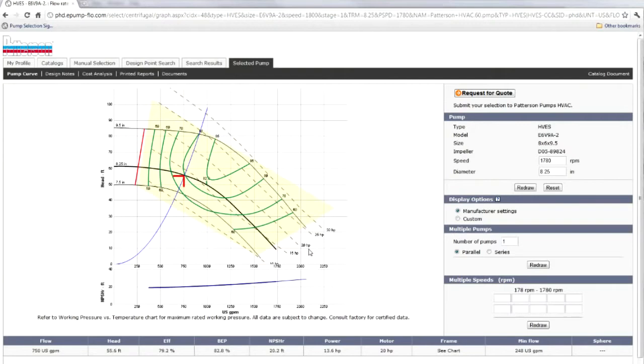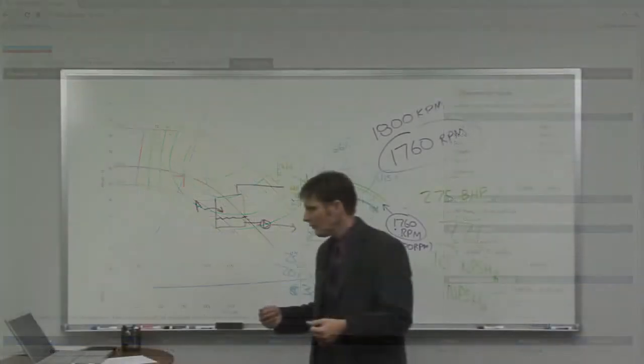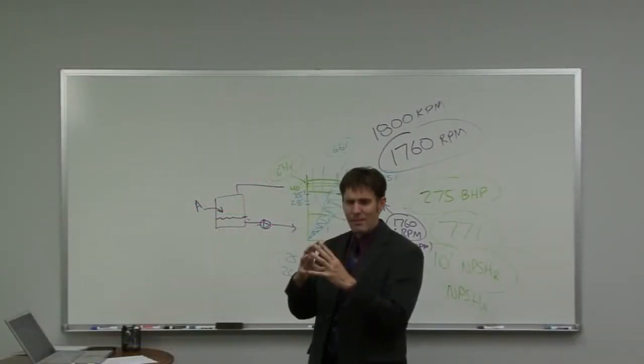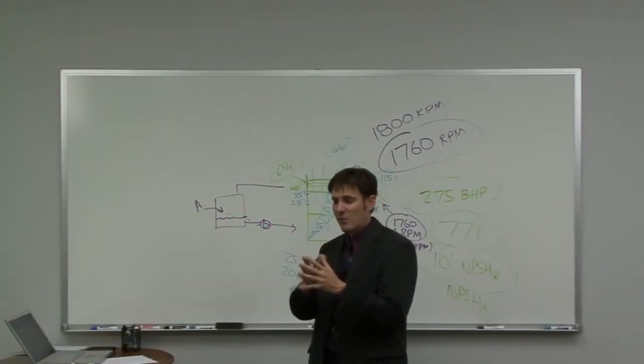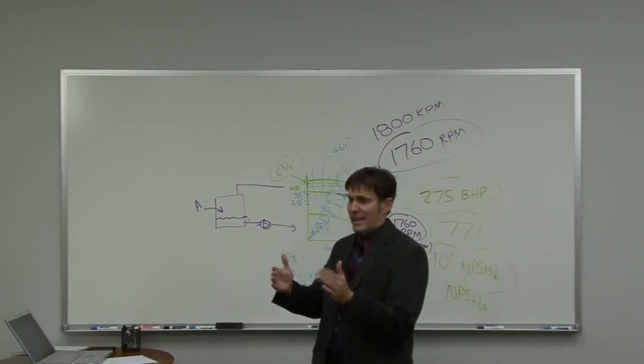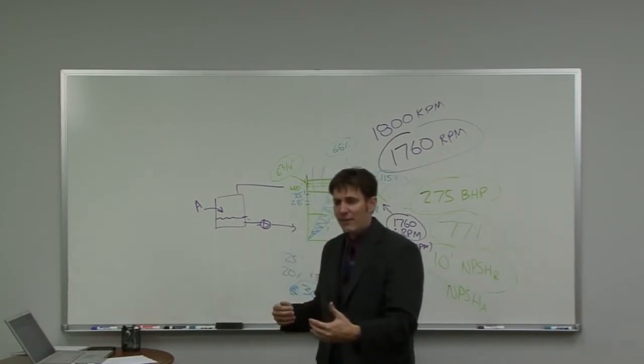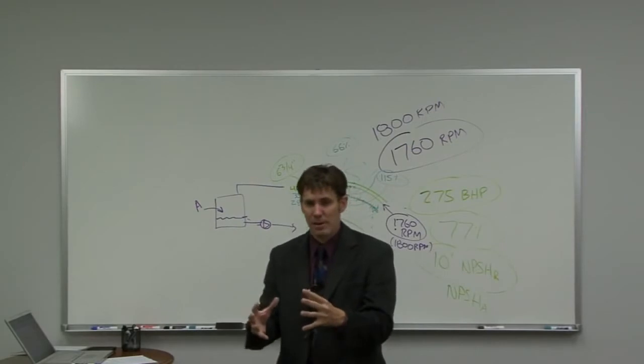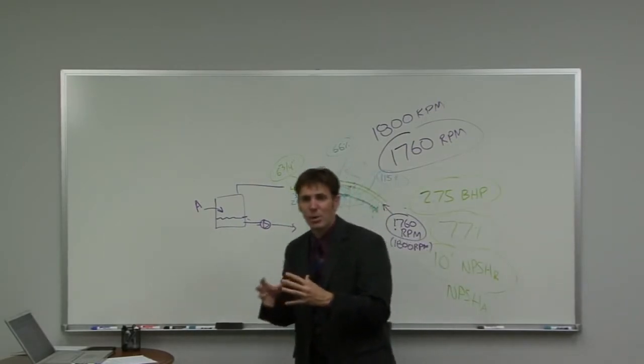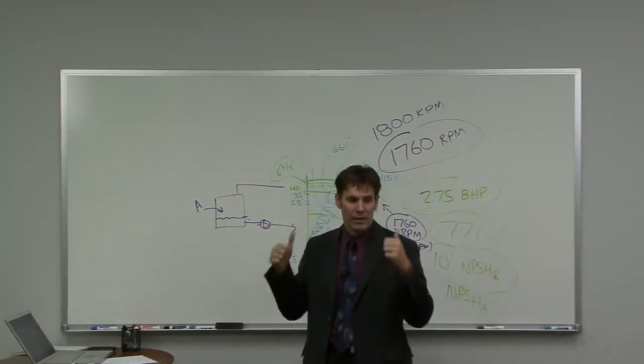But when we look at it realistically, again, we don't have time to talk about this here, but that's telling me that instead of flowing 750 gallons per minute, I've got to flow 900 gallons per minute, and then I'll overload my motor. Well, if I take this pipe system that is sized and with so much pressure to give me 750 gallons per minute, and I now squeeze 900 gallons per minute through that same pipe size, my pressure is going to go up very, very fast.